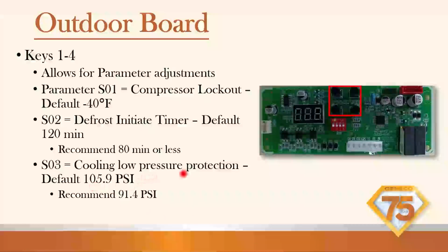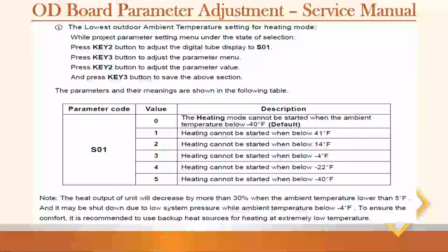That just lowers the low pressure protection. This walks you through the lowest outdoor ambient temperature setting for heating mode. So in the project parameters setting menu, under the state of selection, press key 2 button to adjust the digital tube to S01, press key 3 button to adjust, press key 2 button to adjust the parameter value, and then key 3 to save. So it is confusing the first time, second time gets a little bit faster, third time you're cruising.